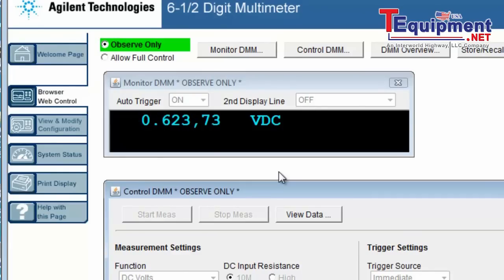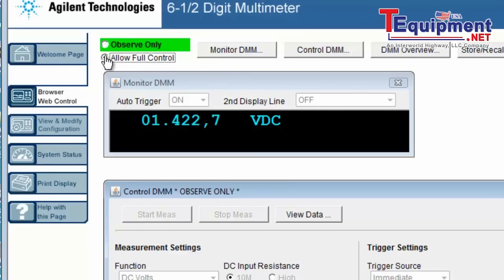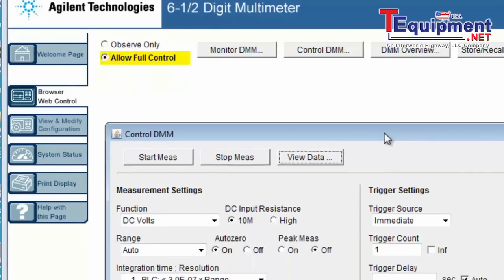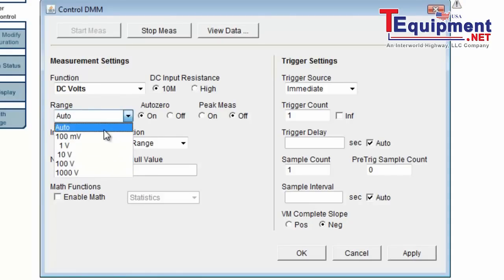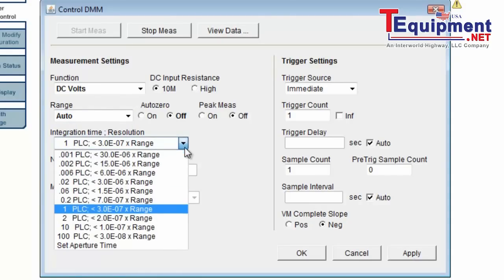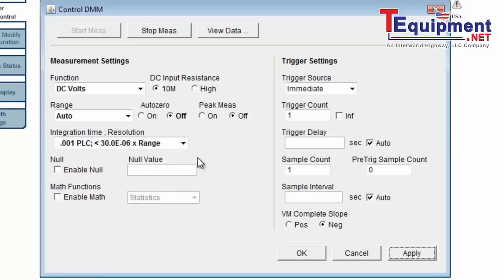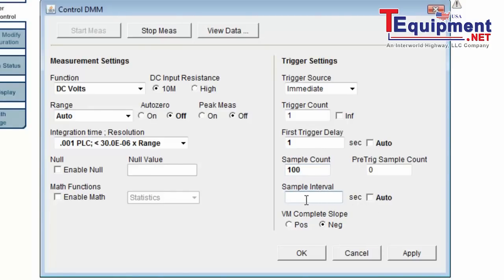So let's go ahead and set up to make some burst measurements. I'm going to select the function I want to use — I'm going to make DC volt measurements. I'm going to stick with the auto-ranging, and I'm going to use a lower resolution so the DMM takes faster measurements. I'm going to set up a trigger delay of one second, then set a sample count of 100, and a 0.02 second sample interval.